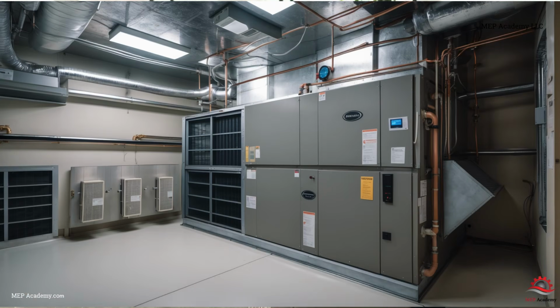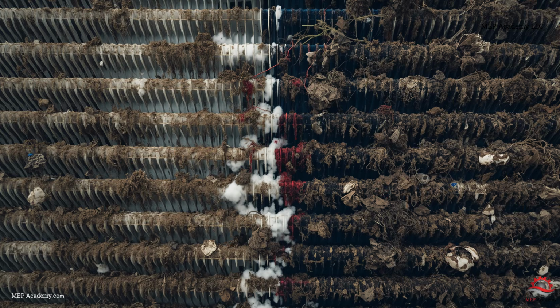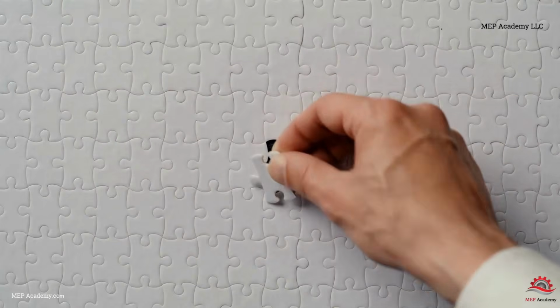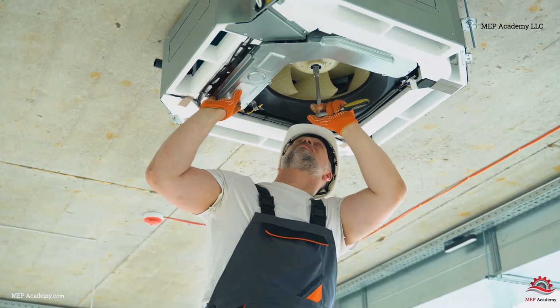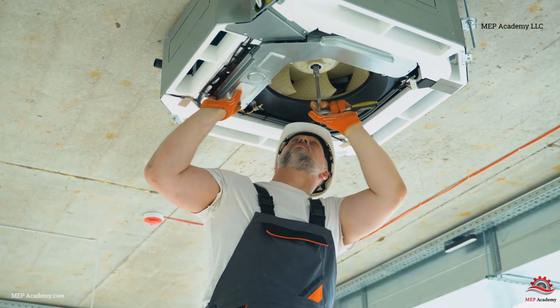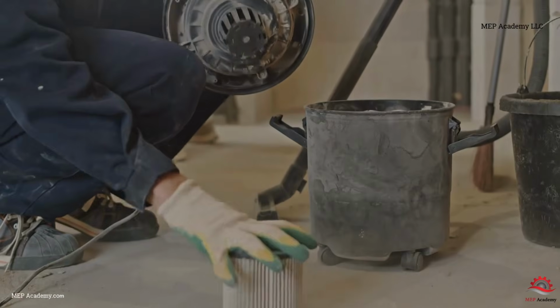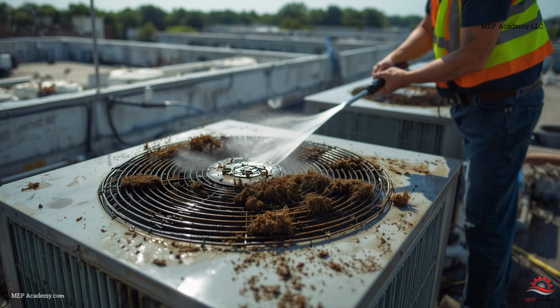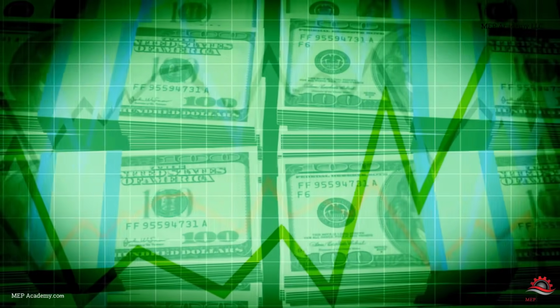Imagine trying to breathe through a heavy blanket. That's essentially what the condenser fan is trying to do when the coil becomes clogged. A dirty condenser coil can reduce efficiency dramatically and may even shorten compressor life. The solution is straightforward. Inspect condenser coils regularly. Follow manufacturer cleaning recommendations. Use proper cleaning chemicals when appropriate. Avoid high-pressure washing that can damage coil fins. A relatively simple maintenance procedure can prevent expensive repairs and significantly reduce energy consumption.